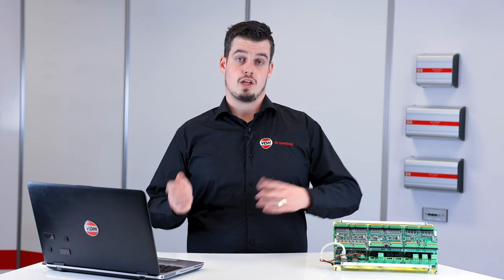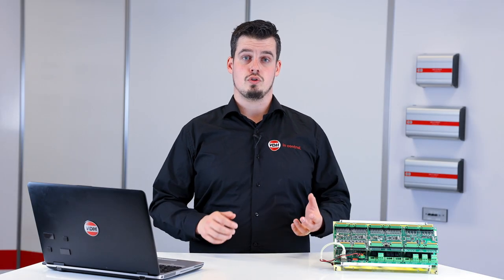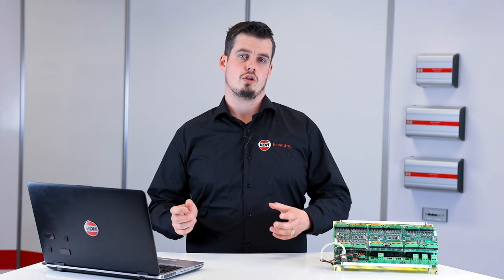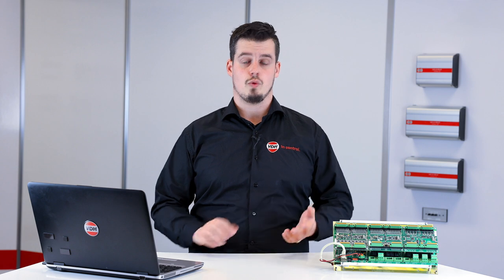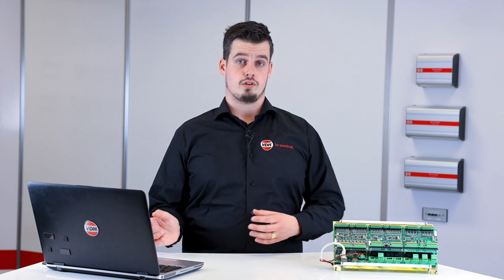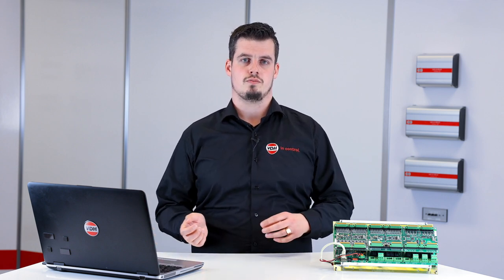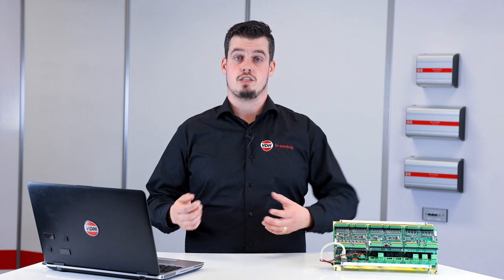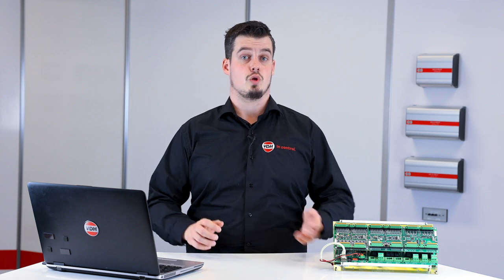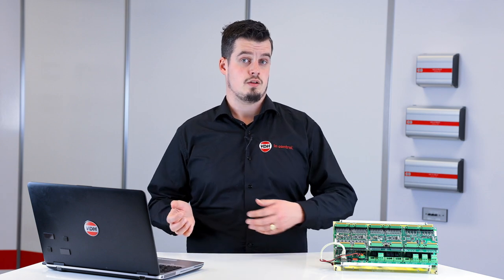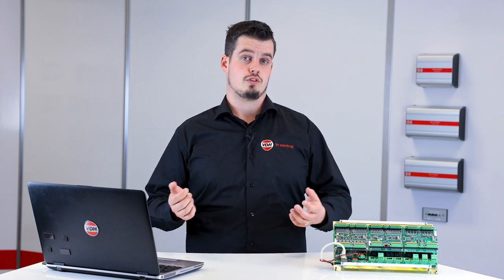The mode can be used for inputs and outputs and are depending on your controller. However, the most common used option within all of our MC3s is the normal and inverted option for digital inputs and outputs, which, as the name might suggest, inverts the signal, meaning high becomes low and low becomes high. This is often used for alarm inputs and outputs.